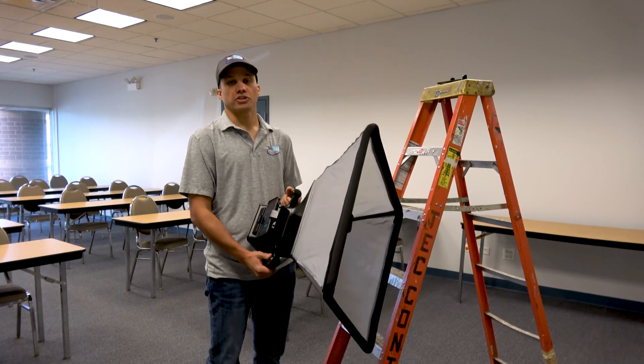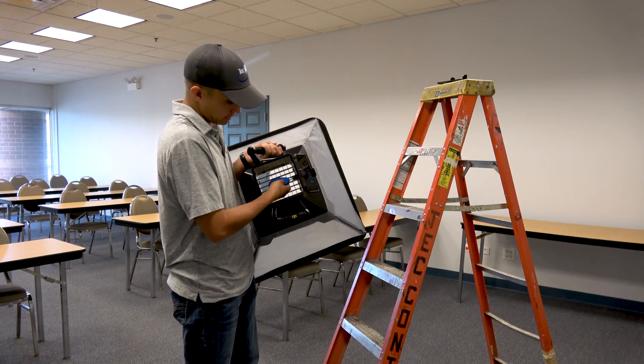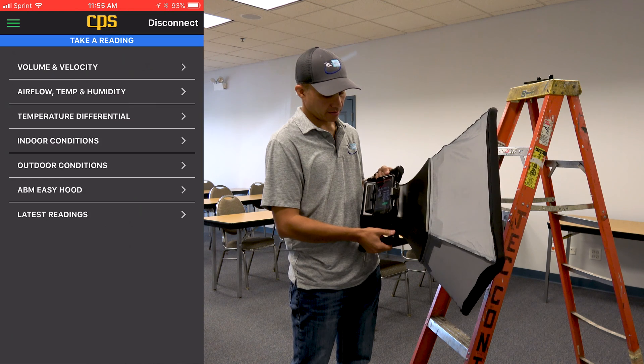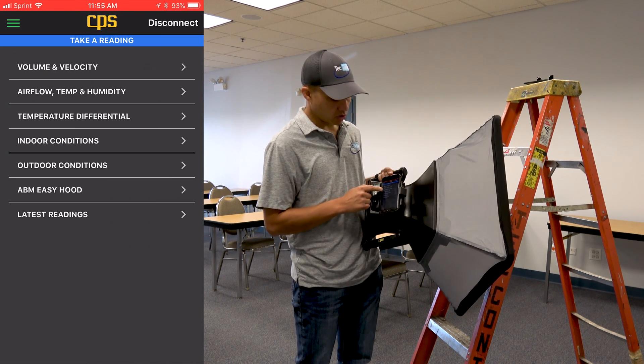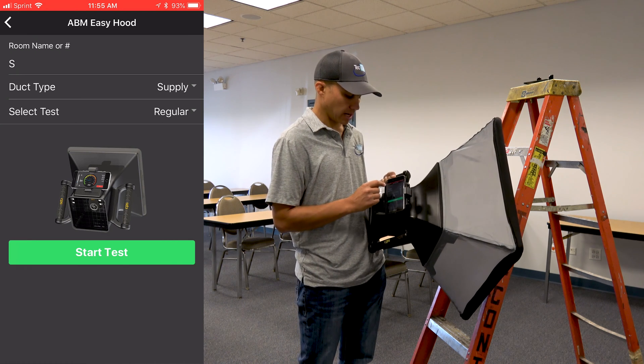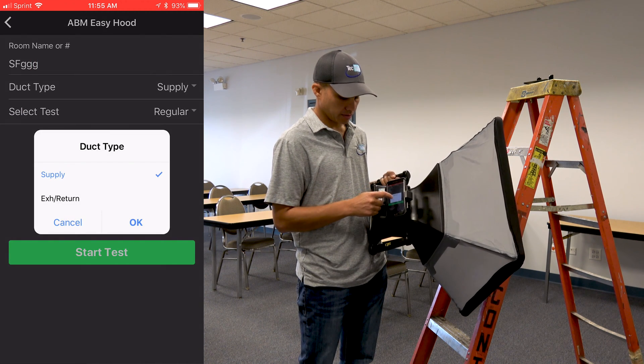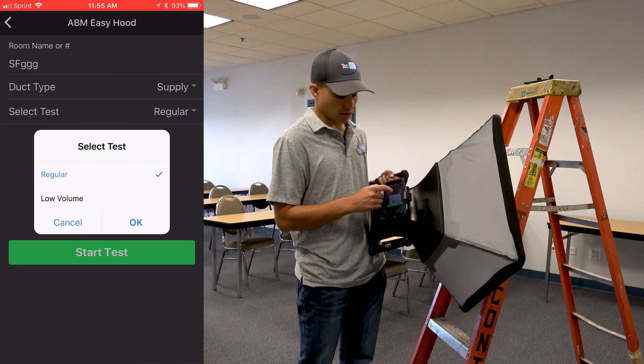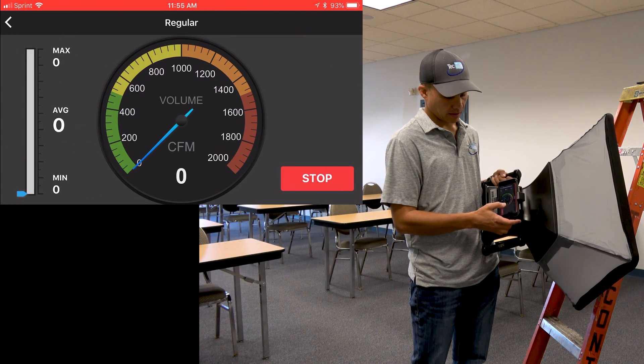We're doing a couple of measurement readings to show you how easy it is to use this hood — hence the name Easy Hood — versus using just a little probe by itself. First, turn on the measurement device, then in the software app hit Scan, it finds the device, and now it's connected. Go all the way down near the bottom to where it says Easy Hood and click on it. There are only a couple of things to set up: you can name the room for reporting purposes, pick whether it's a supply, return, or exhaust, and then choose either a regular test or a low volume test. I'll do a regular one now and explain the low volume option in a moment. Then hit Start.